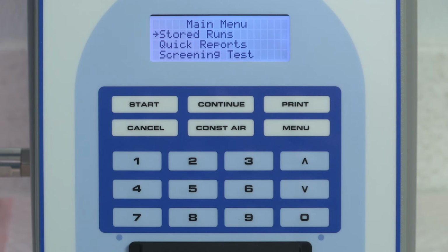The VERISCAN Leak Tester system can print custom reports that summarize daily, weekly, and monthly leak testing results. For example, a report can be generated that lists all the endoscopes that failed the leak test within the past 30 days. The unit retains 2,500 records before it begins overwriting the oldest to make room for new records.